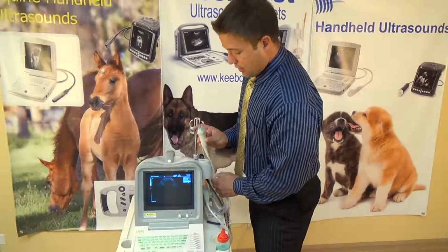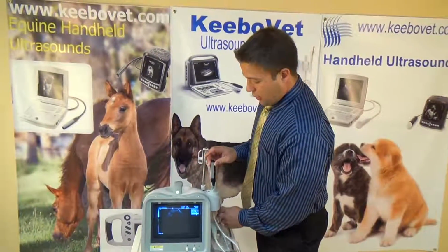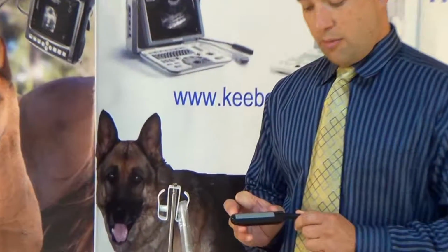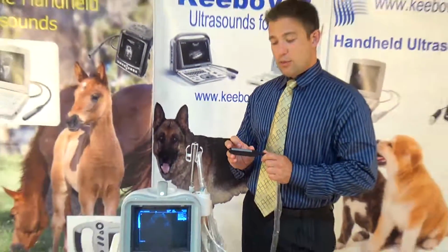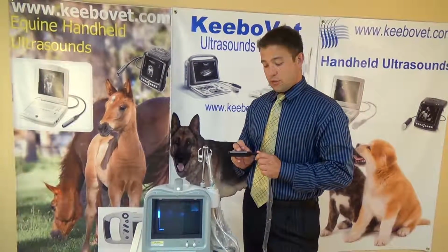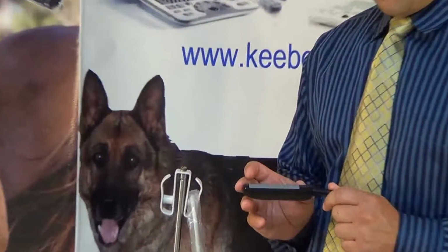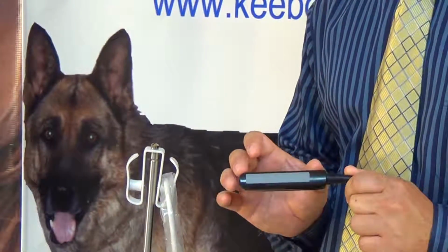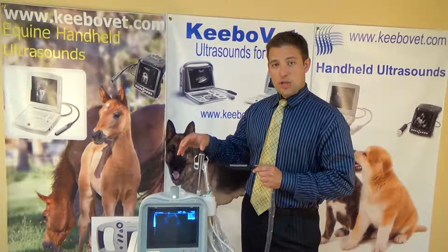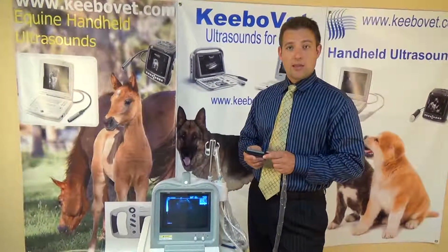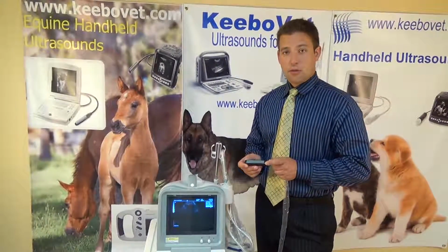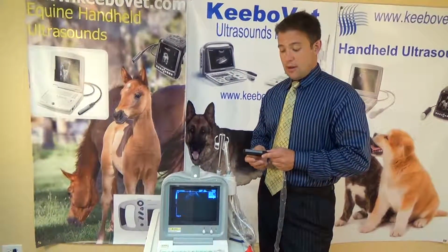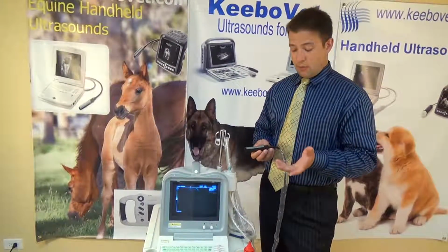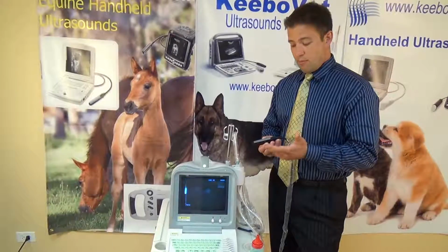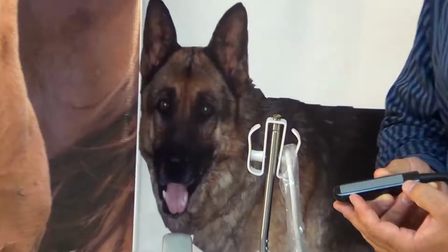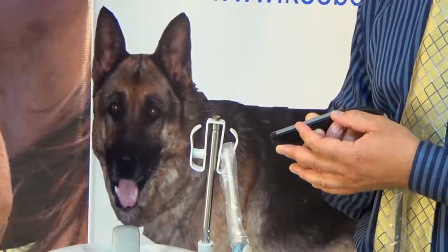The other probe that we have here is a linear or rectal probe, and the great thing about this one is the size of the probe. So a lot of the competition, once again, provides you with small probes, so small footprint. Ours is 70 millimeters, 7 centimeters, and that is good because the larger the probe size, the larger the screen shot will be. So if you're looking at ovaries, for example, or whatever the case is on an animal, you want to have as much of an image as possible rather than a small image, so you can see everything on one screen. So, to recap, a lot of the companies that make other machines will say you have 40, 45, 50, so definitely a significant difference between our 70 and what everybody else has.